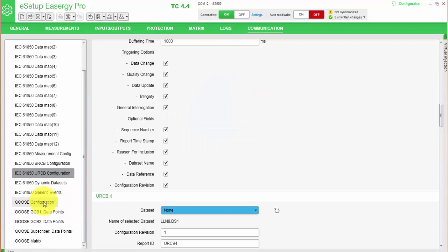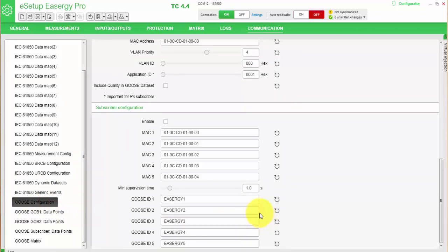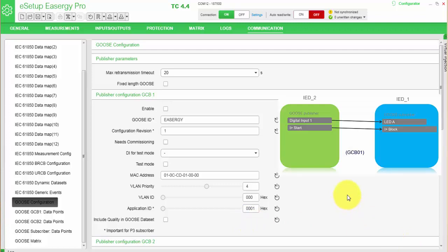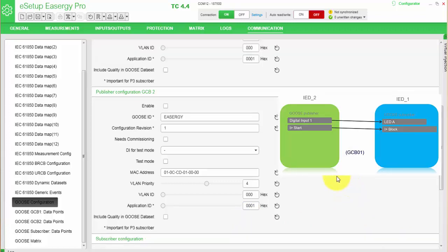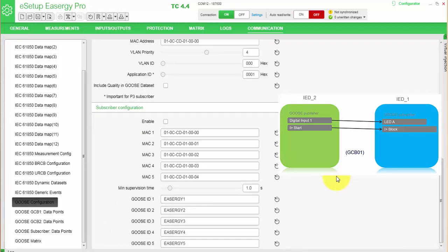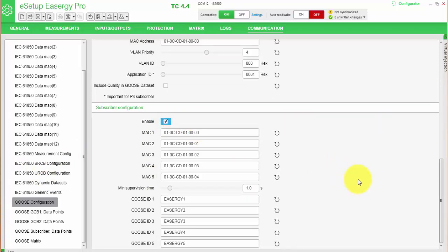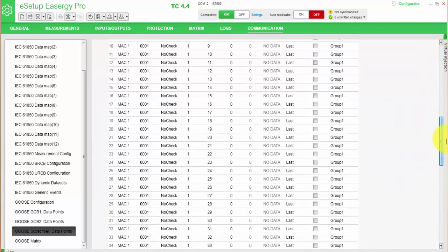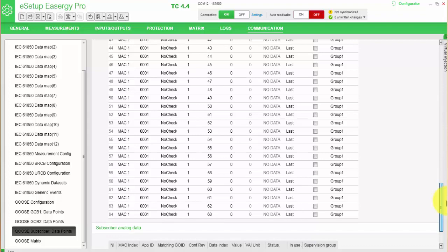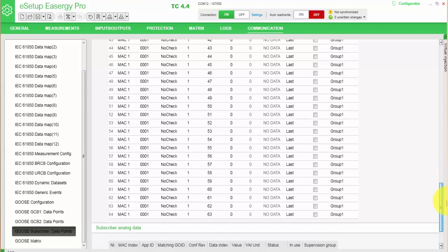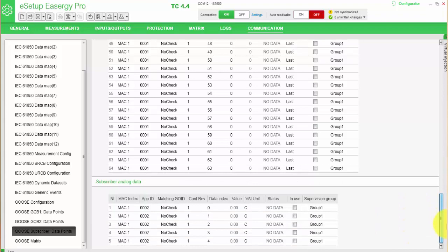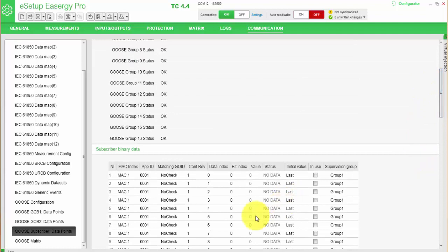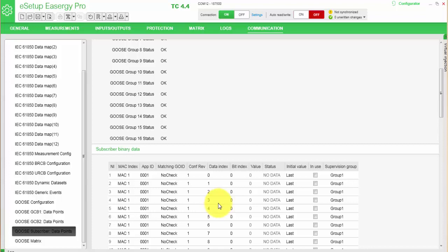And we go next to the GOOSE configuration. So this relay is the IED_1, so it will receive the GOOSE signal from another IED_2, which we have to configure later. We will only do the subscriber configuration. So in this menu we will enable the subscribing, and we can define the MAC addresses we can receive from 5 different MAC addresses. Subscribing we can receive maximum 64 signals from several other devices via GOOSE message, and we can receive 5 analog signals. In this case, we need to know the publisher MAC address, application ID, and configuration revision, as well as we will need to separate messages inside the GOOSE log with the data index, and we will put it into use.